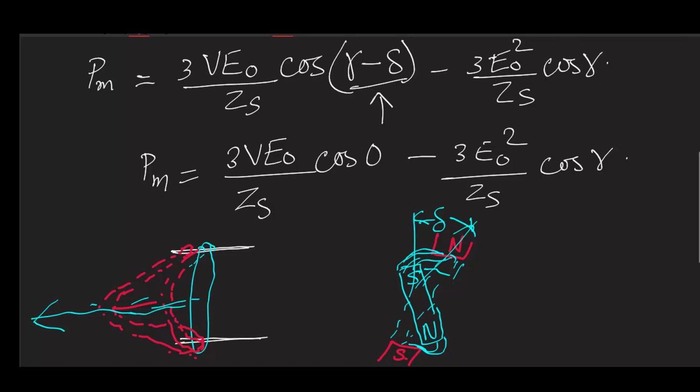Now the same thing happens, and that is known as pull out torque. When the delta value is so high that the magnetic lines of force are not able to pull it back or exert any kind of pull or torque on this shaft to make it aligned, then your motor stalls. That is what is known as stall torque or pull out torque for a synchronous machine.